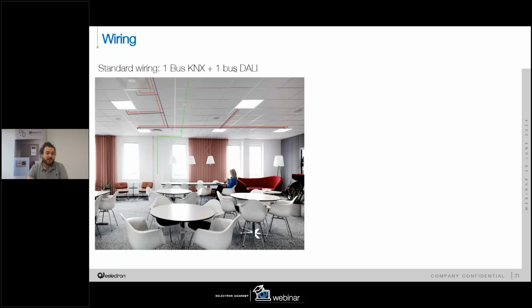Another example that could be very useful to understand the new power and the new function that the multi-master controller gateway between KNX and DALI can bring is this example, where we can see that we have two ways to integrate push button, sensor, and lighting system. The first one is the common one that you already know. So you have the push button and the sensor wired in KNX, and all the luminaires are wired with the DALI bus and, of course, DALI ballast.